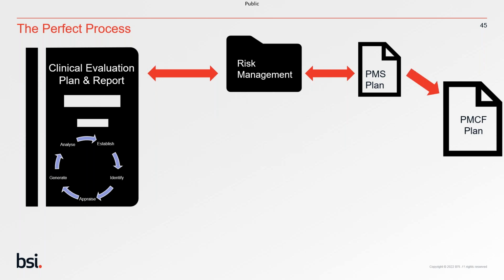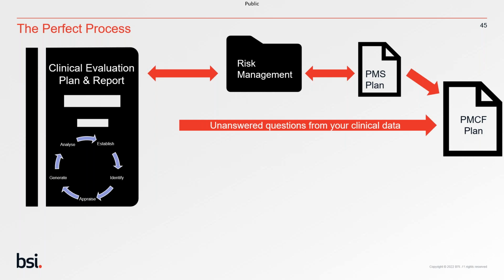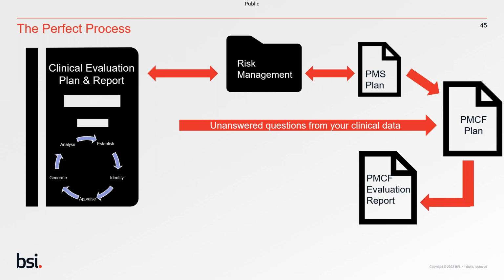And as part of your post-market surveillance plan, you need to have a post-market clinical follow-up plan, okay? So that will talk about the general and specific activities. But also feeding into your PMCF plan from your risk management and identification of activities are, of course, those unanswered questions that you hold from your clinical data. Maybe there's something on a specific variant that you need to gather. And it's the output of those activities from your post-market surveillance plan and your post-market clinical plan that follow into your post-market clinical evaluation report.